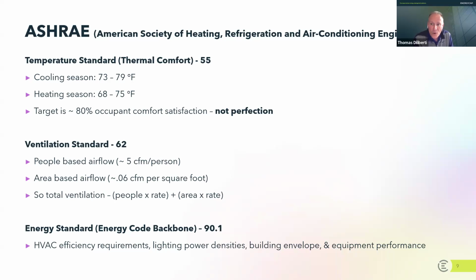So if you're basing your calculations or you're basing your system control by people, it's 5 CFM. If you're basing it on area, what you should do is you should use 0.06 CFM per square foot. Or to do a quick calculation for you, if you had a 1,000 square foot space, and 1,000 square feet is roughly the size of a typical classroom within a school building, what that would mean is you need 1,000 times 0.06, or you would need about 60 cubic feet per minute of fresh air flowing into that space in order for it to be appropriately ventilated.